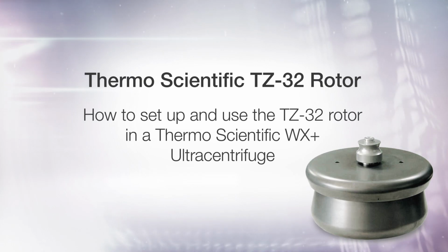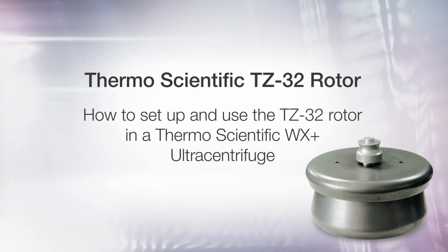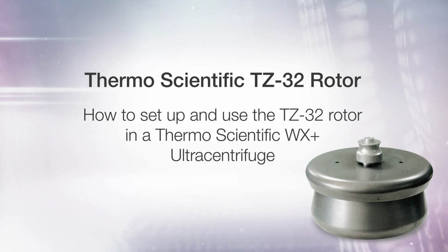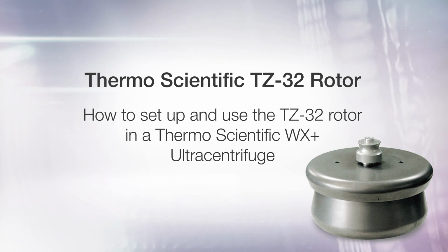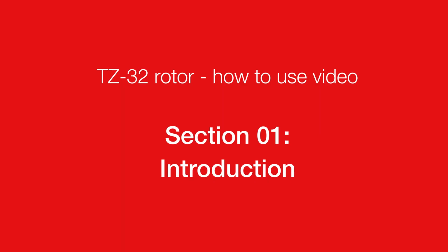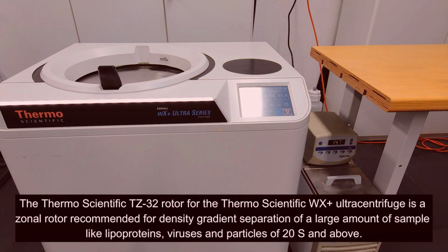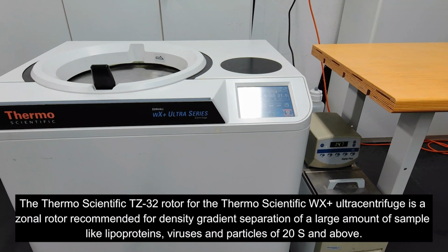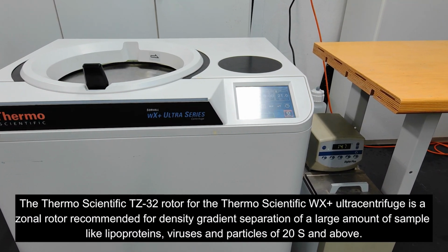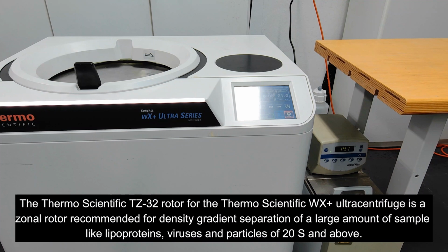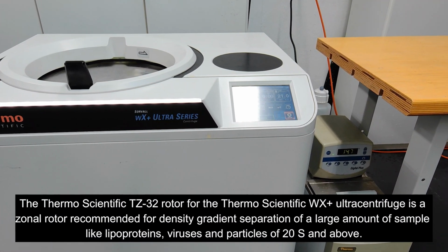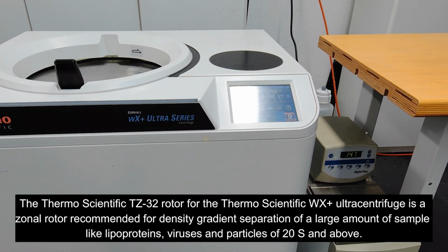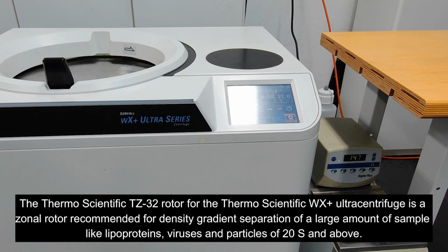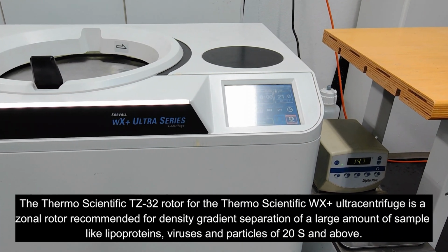Thermo Scientific TZ-32 rotor for the Thermo Scientific WX Plus ultracentrifuge. How to use video. Section 1. Introduction. The Thermo Scientific TZ-32 rotor for the Thermo Scientific WX Plus ultracentrifuge is a zonal rotor recommended for density gradient separation of a large amount of sample, like lipoproteins, viruses, and particulates of 20S and above.